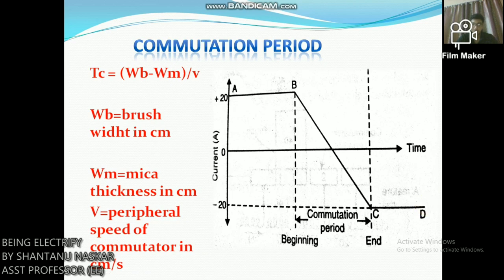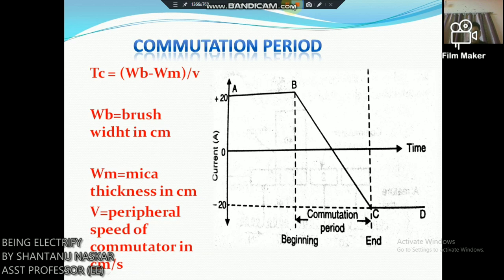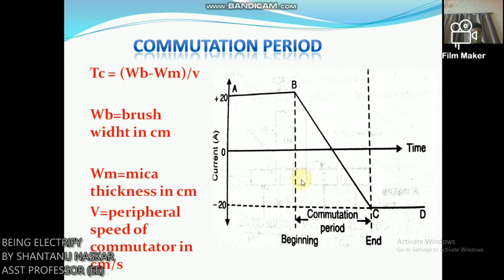This figure shows the current-time graph for coil A undergoing commutation. The horizontal line AB represents a constant current of 20 amperes up to the beginning of commutation. From the finish of commutation it is represented by another horizontal line CD, on the opposite side of the zero line and the same distance from AB — the current has exactly reversed. The way the current changes from B to C depends on the conditions under which the coil undergoes commutation. If the current changes at a uniform rate (a straight line), it is called ideal commutation, and no sparking will take place between the brush and the commutator.